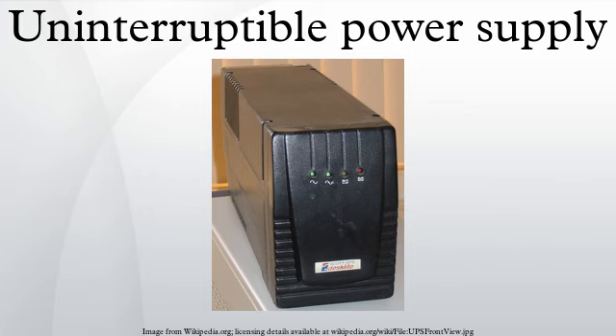This allows the UPS to achieve very high efficiency ratings. When the power conditions fluctuate outside of the predefined windows, the UPS switches to online double conversion operation. In double conversion mode, the UPS can adjust for voltage variations without having to use battery power, can filter out line noise and control frequency. Examples of this hybrid double conversion on demand UPS design are the HPR 8000, HPR 12000, HPR P12000/3 and the Eaton Blade UPS.